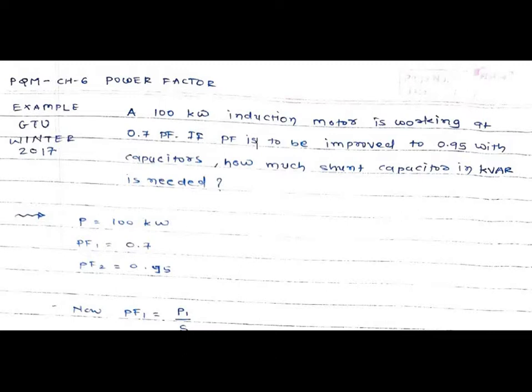Today we will discuss an example from Chapter Number 6, Power Factor, of the Power Quality Management subject. This example was asked in the GTU examination of Winter 2017. The problem: a 100 kilowatt induction motor is working at 0.7 power factor. If the power factor is to be improved to 0.95 with capacitors, how much shunt capacitor in KVAR is needed?